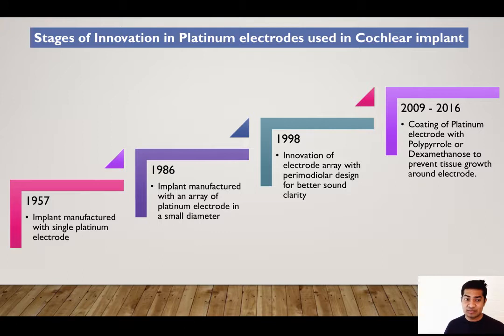Initial research defined platinum as biocompatible, but it actually had a bit of fibrous tissue growth. Recent research between 2009 and 2016 has shown reduced growth of tissue around the platinum electrode by coating it with special biomaterials such as polypyrrole or dexamethasone. These have been tested in animals. Further research shall provide significant breakthroughs. Do cochlear implants fail? Yes, they do, for several reasons. For instance, impact damage can lead to failure of the device, or improper insertion of the electrode within the cochlea can lead to device failure.